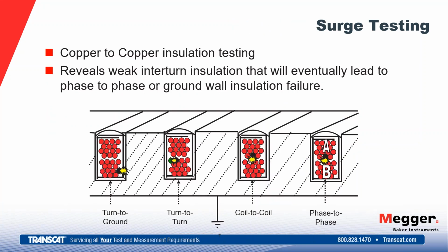The final static test that we are going to perform will be a surge test. And a surge test has the unique ability to deliver a nonlinear drop of voltage across the windings. And so here we have a difference between turns. We have a voltage drop between turns. That way we can strictly evaluate copper to copper insulation. It will reveal the weak interturn insulation that eventually leads to a phase-to-phase or ground wall insulation failure.